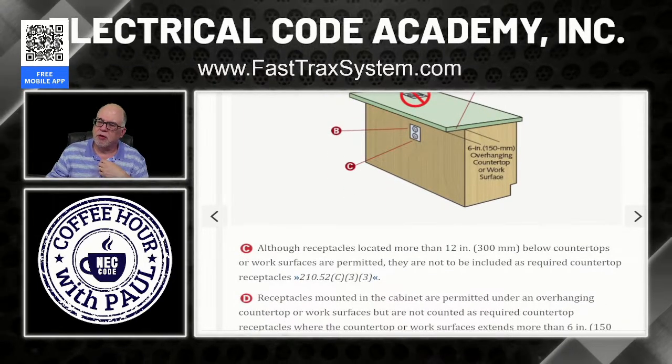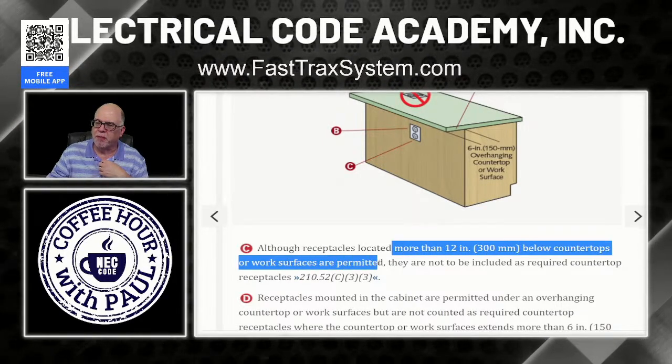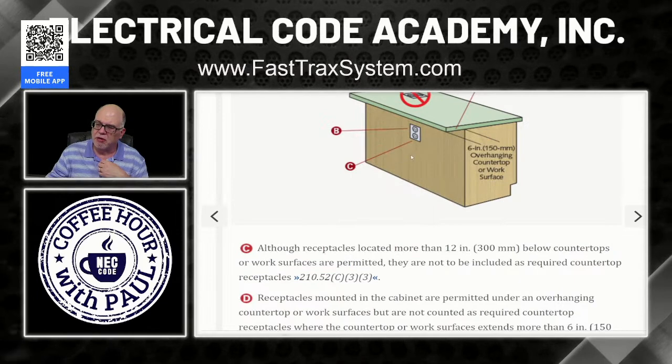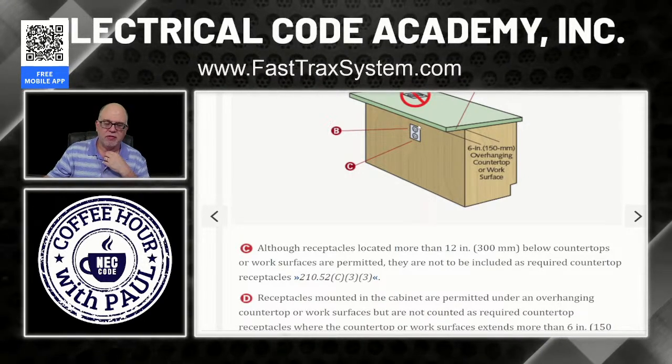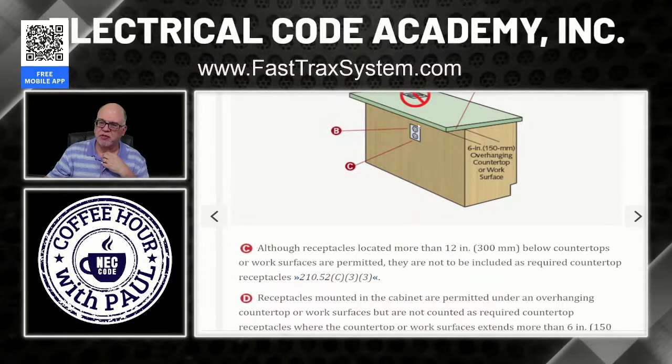All right, what about C right here? Although receptacles located more than 12 inches below the countertop or work surface are permitted, so yeah, I could have one down lower, they're not going to meet the requirement to serve the countertop because they can't be more than 12 inches below, and they can't be under an overhang that extends more than 6 inches. I couldn't put the receptacle under here.